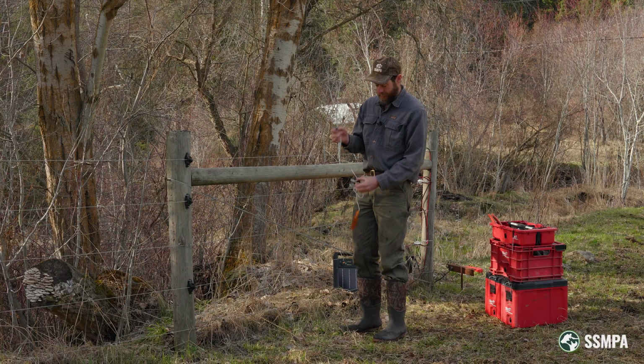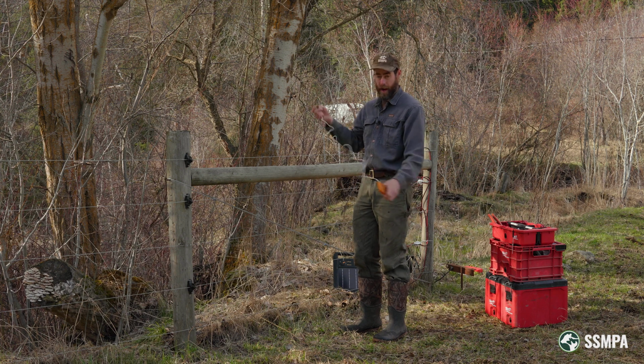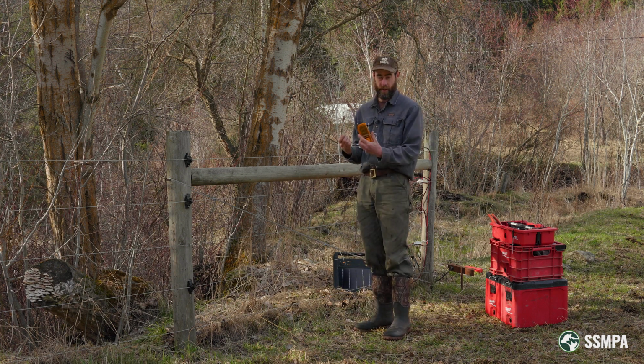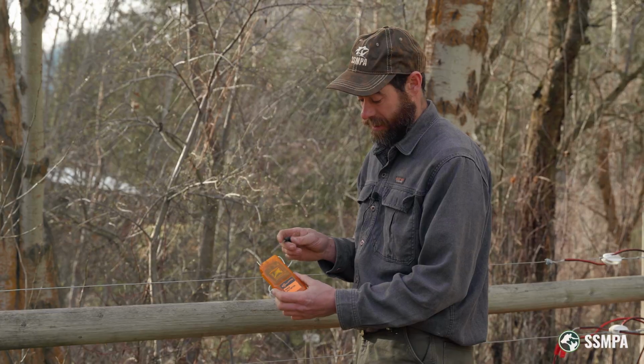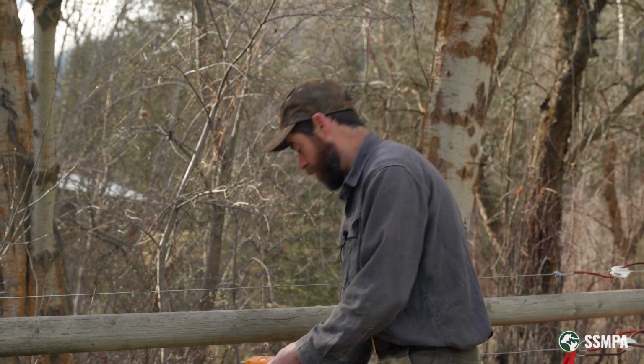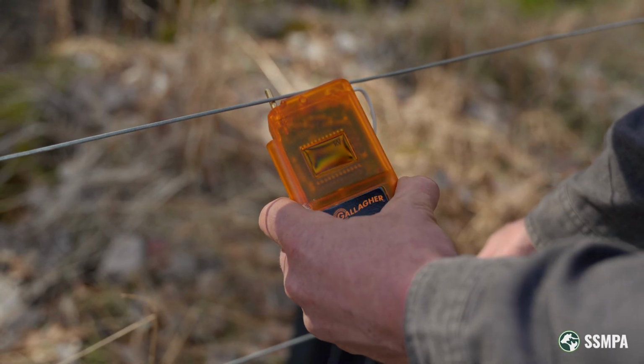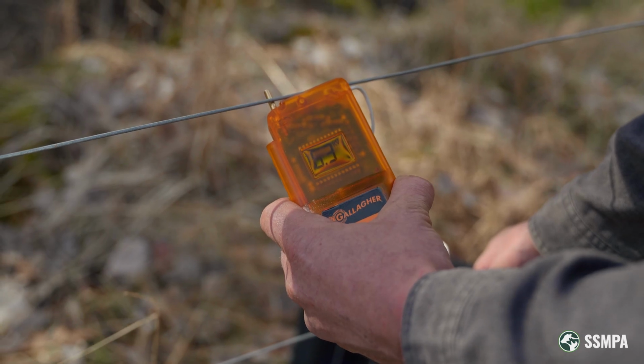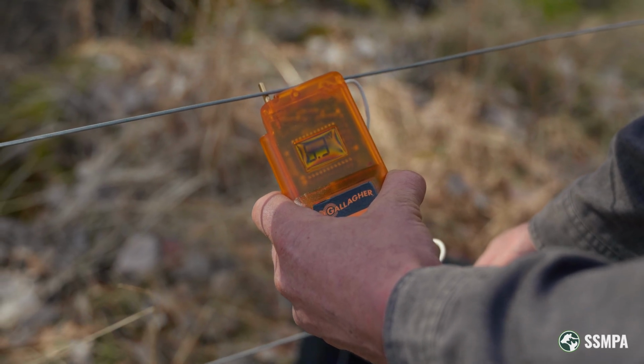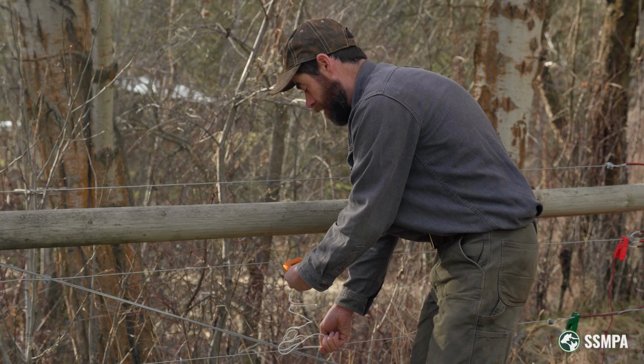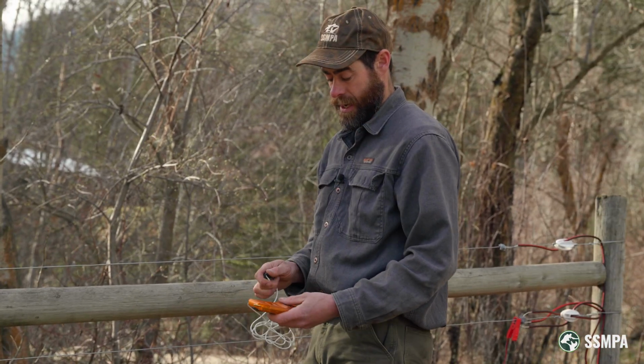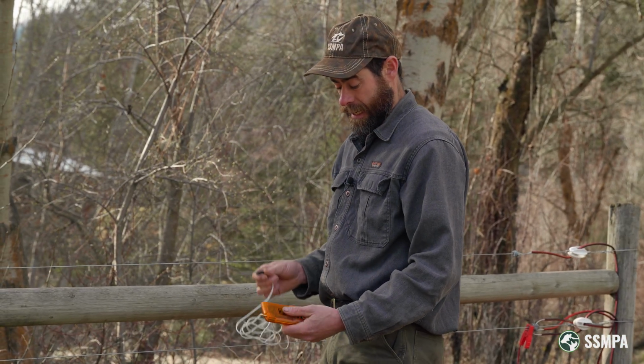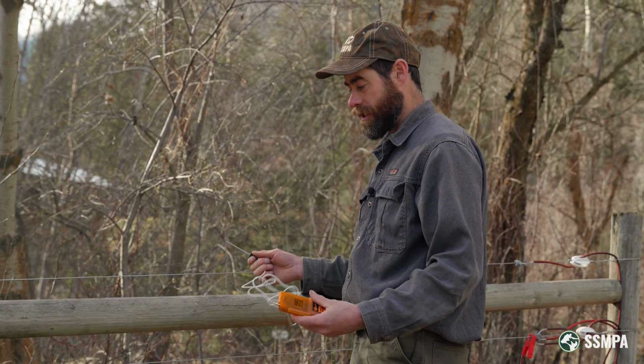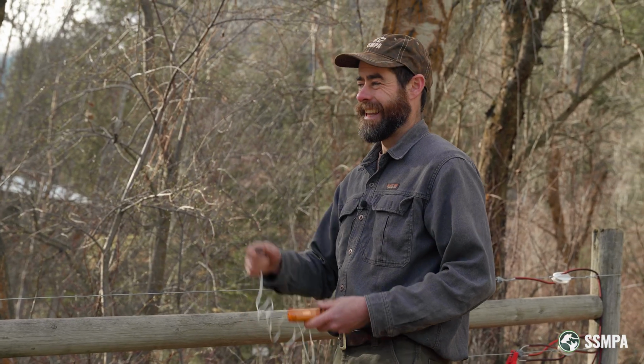A slightly more expensive but more accurate option is a digital readout fence voltmeter like this one. When we do the same test with this voltmeter, we're actually able to see a number. In this case, the fence is reading 6.3 kilovolts, or 6,300 volts. This is a lot more accurate, and these digital voltmeters can also be used for additional troubleshooting, like testing your fence grounds.